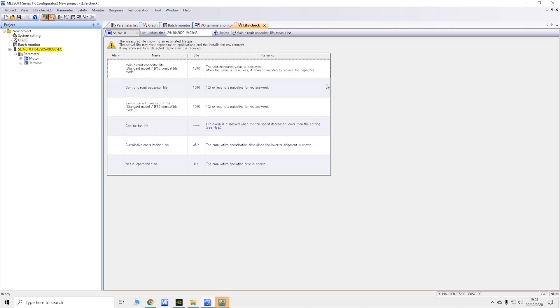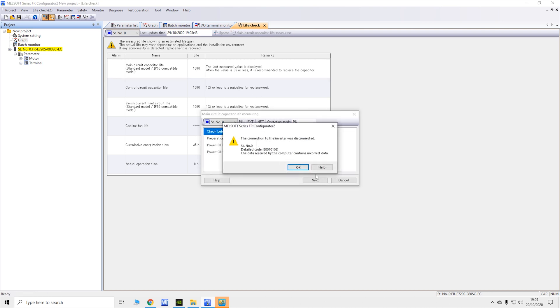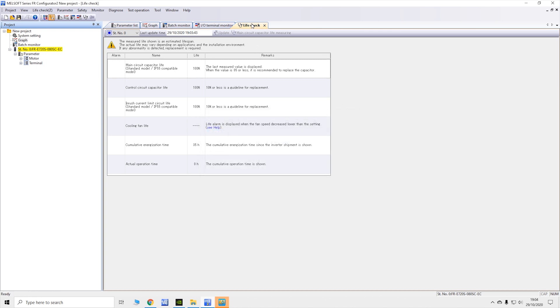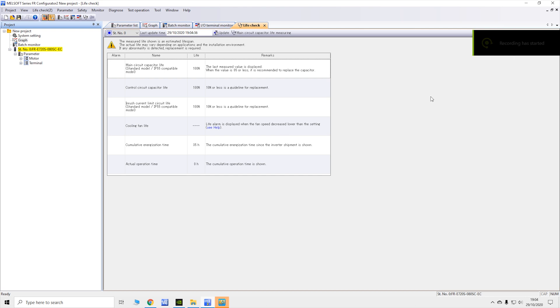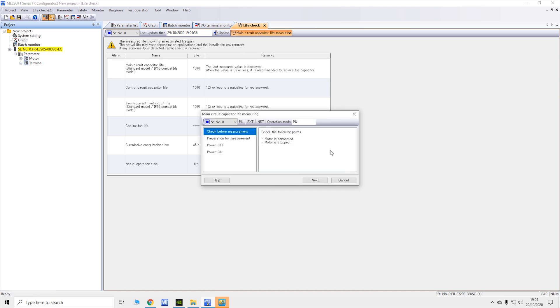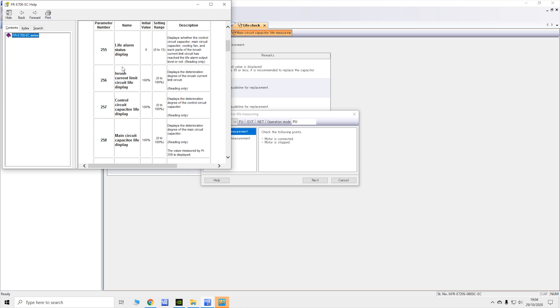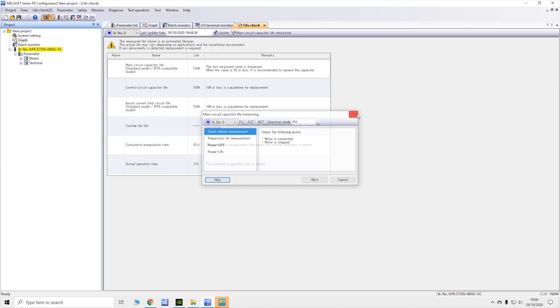You can also do a Main Circuit Capacitor life measurement. I can't do mine because my motor is too small for a proper measurement on this drive, but if your drive is close to the motor you should have no problem. Note: I keep losing connection to my drive because I'm using a quite long USB cable — be aware, don't use too long a USB cable. In here you can do your live checks and the instructions are all provided. Even the Help section covers it all. You literally can't go wrong — just follow the instructions.